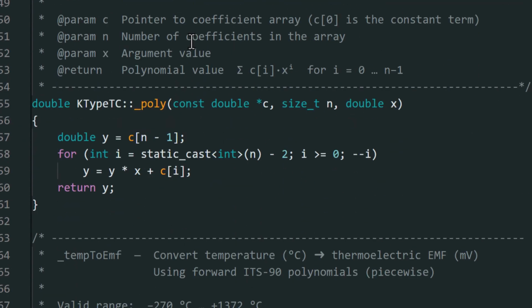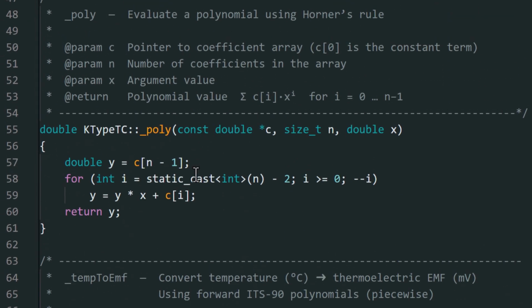So let's go down to our polynomial equation. This polynomial can be used in either direction, to convert voltage to temperature or temperature to voltage, which we need for the cold junction compensation. I didn't make up this polynomial, I got it from the ITS-90 standard.